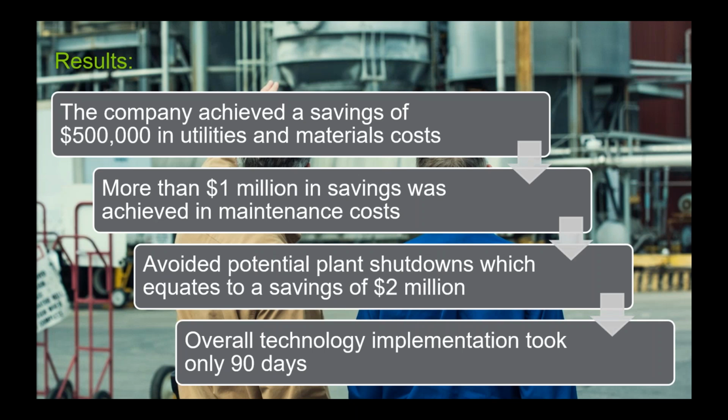Shutdowns, we saved several shutdowns just because we put standard work in our IntelaTrac system. And we would look for spare pumps. We would make sure that the equipment was operated properly. We found things that we were surprised at. We found motors that wouldn't start when they should have started. And if they had not worked, we would have been shut down. We found other pieces of equipment that were near failure. And we found those before they failed based on the IntelaTrac.